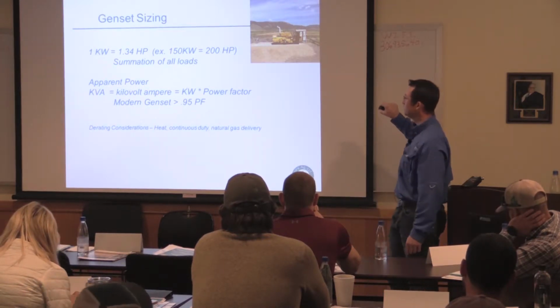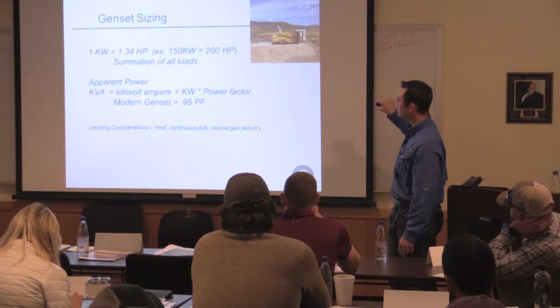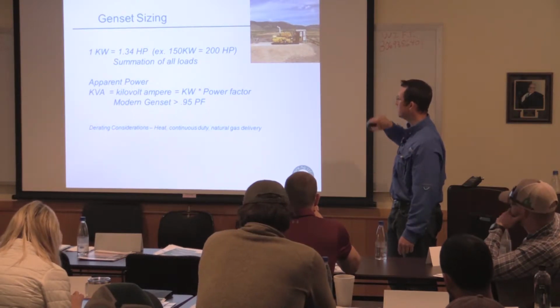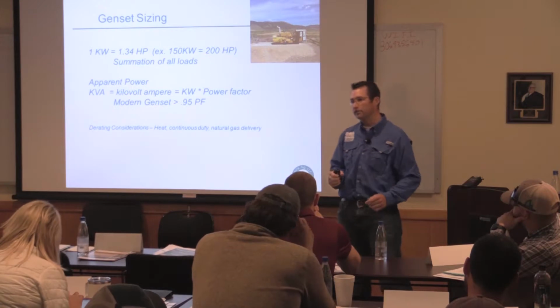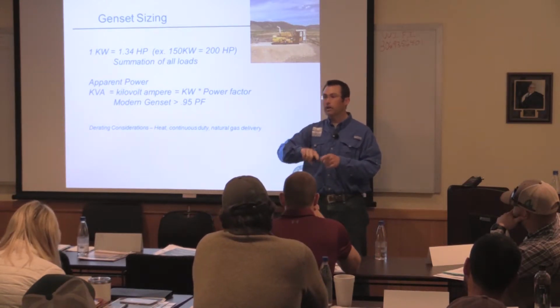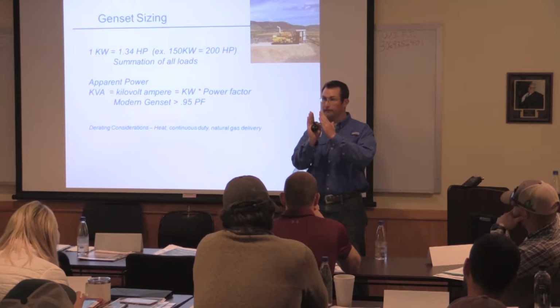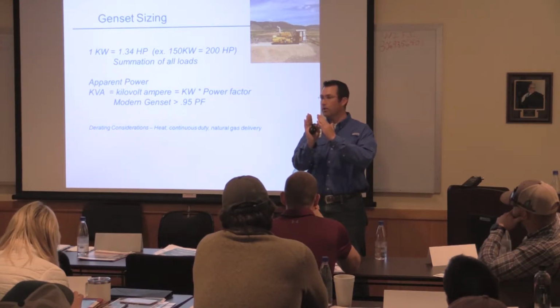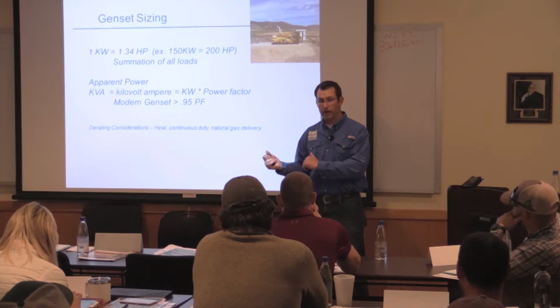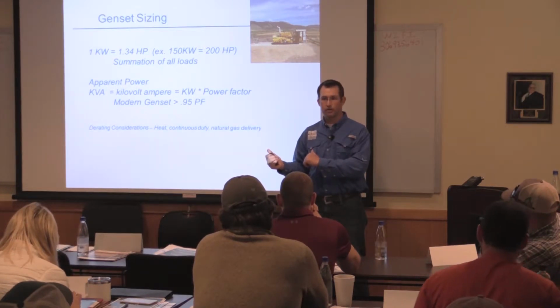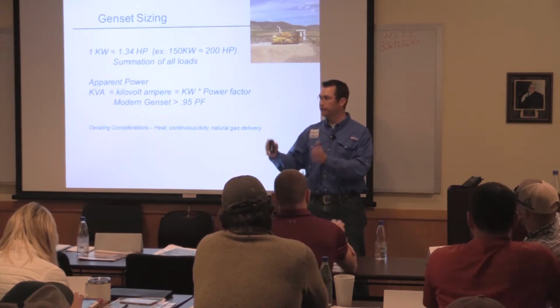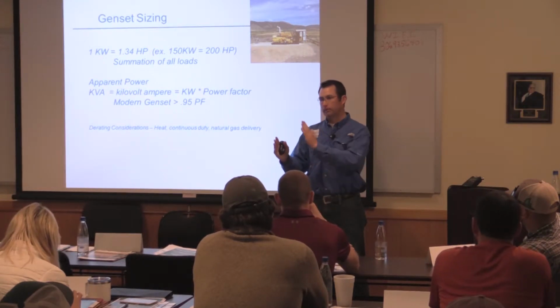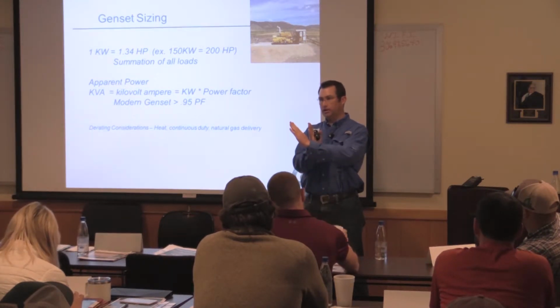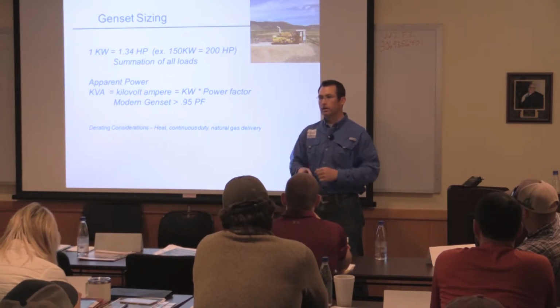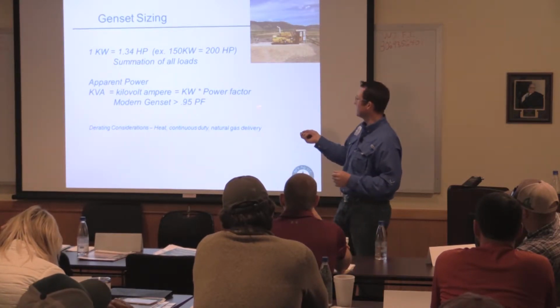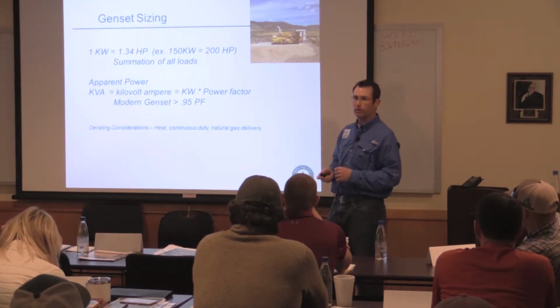Another thing you want to pay attention to is apparent power. Your modern gensets are going to have really close to unity power. What that means is that there's a phase difference between where your volts are at and where your amps are at. Okay, if they're slightly out of phase, you lose a little bit of power, and that's referred to as the power factor. That's really important in these scenarios because you're going to use inductive motors on these well pumps. What that means is that by default they have a lagging power, which means the volts usually is a little bit before the amps. And you're going to reflect that in the number of power factor. Okay, and that's something that can be measured but must be accounted for.